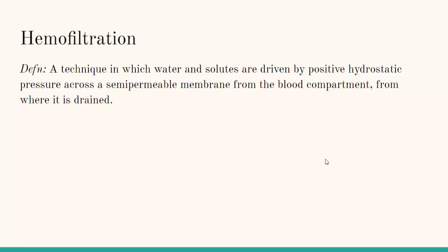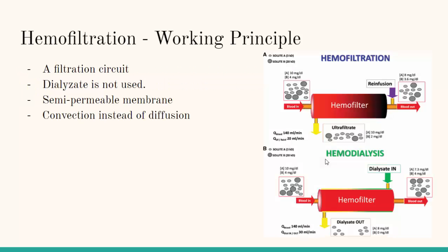The effectiveness of convection mainly depends on the size of the dialyzer membrane pores. It has similar features with hemodialysis as hemofiltration: distribution volume and protein binding percentage. However, dialysate is not used with hemofiltration. Instead, a positive hydrostatic pressure activates the water. How does hemofiltration work? Hemofiltration works by removing large volumes of plasma water across the dialysis membrane using a pressure gradient or transmembrane pressure. The driving force is a pressure gradient rather than a concentration gradient.